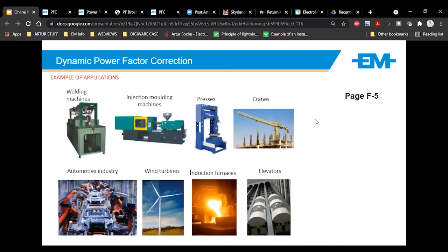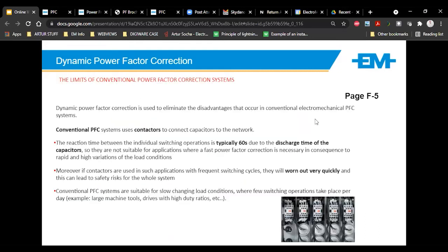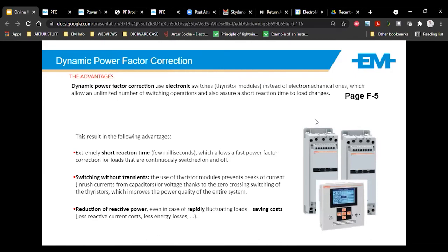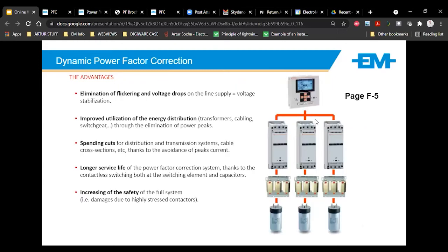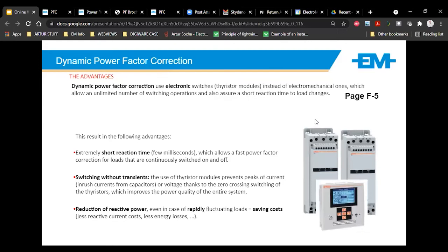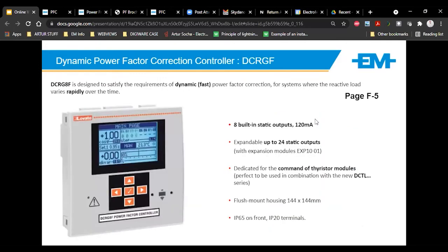So typical fast switching would be welding machines, pressers, cranes, and so forth. You'd need to rather look at what we call dynamic power factor correction, where we use thyristors instead of contactors to do the switching. So on these type of systems, you're going to have a lot more switching times out of the device versus a contactor. I've seen counters on the DCR-G8 with Thyristor-based systems where they've switched in capacitor banks millions of times already, versus something you would not be able to achieve using contactors. All right. A big advantage is that it switches without a transient. How it does that, it makes sure it switches in at what we call the zero crossing of the signal. So it doesn't create any spikes. The controller that's most compatible with this would be the new DCR-G8F, which is specifically built to work with Thyristors.